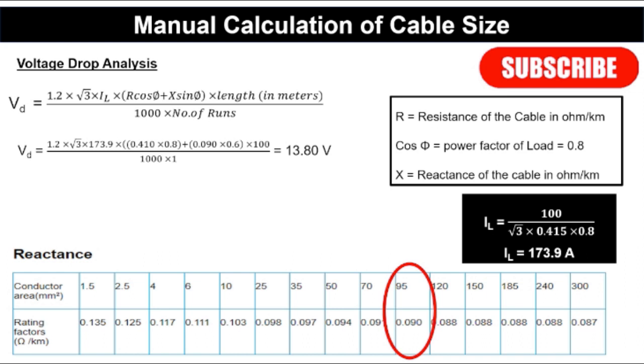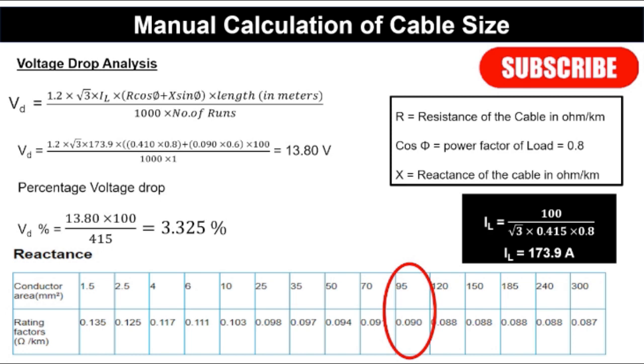The percentage voltage drop is: VD% = 13.80 × 100 / 415 = 3.325%, approximately 3%. If your load operates correctly at this voltage drop, or if your client accepts it, then the cable size of 95 mm² is acceptable. If not, you need to increase the cable size to reduce the voltage drop. This will be demonstrated in the next lecture using the Excel sheet and ETAP, where increasing or decreasing the allowable voltage drop percentage changes the cable size accordingly.